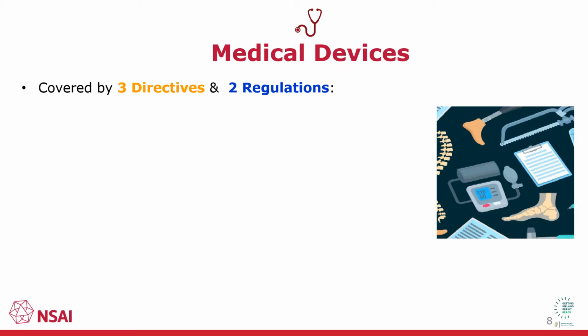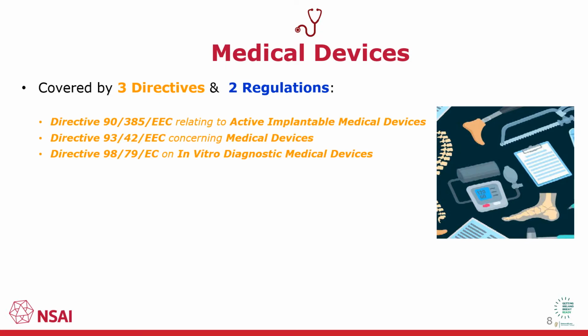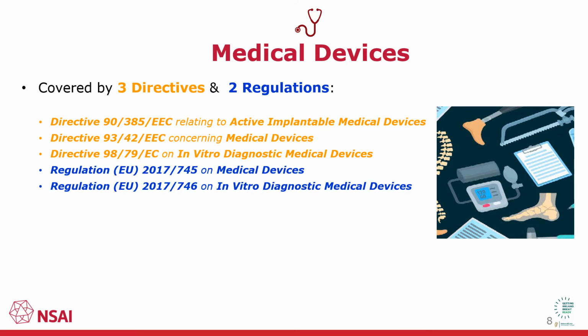Medical devices are currently covered by 5 directives and regulations, the 3 older directives and the 2 new regulations. We are currently transitioning to the medical device regulations, which will replace the active implantable medical devices and medical device directives. COVID has had an impact on this sector, and the 2 MDDs were to be withdrawn in May 2020, but the EU have extended this by 12 months.